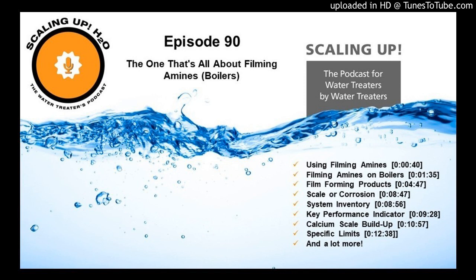I mean, you can go ahead and either leave your conductivity set point for your surface blow down, or you can lower it just a little bit if you want to, but just get it out. Blow it down, bleed it off, whatever you want to call it, but get it out of there. Because ultimately, what leaving loose debris does is leaves increased surface area in there.